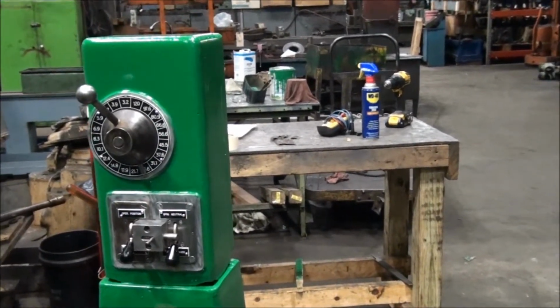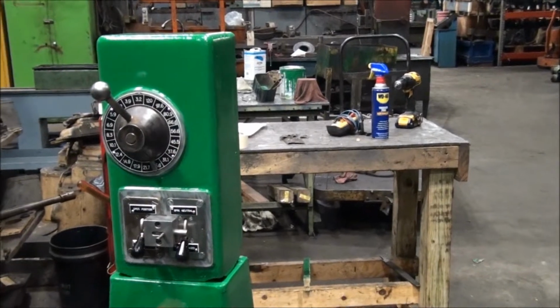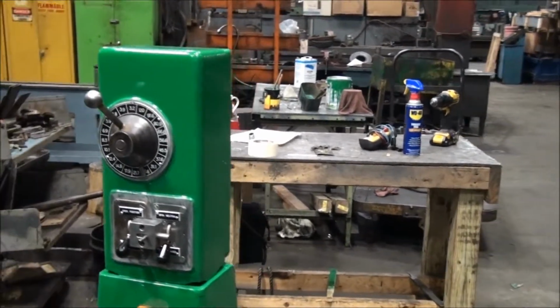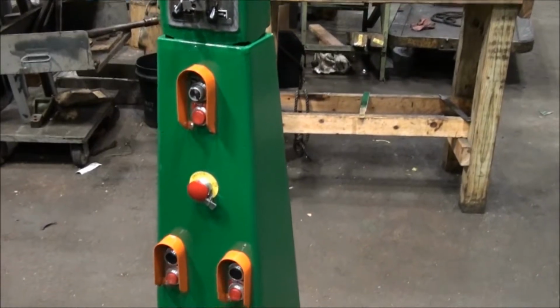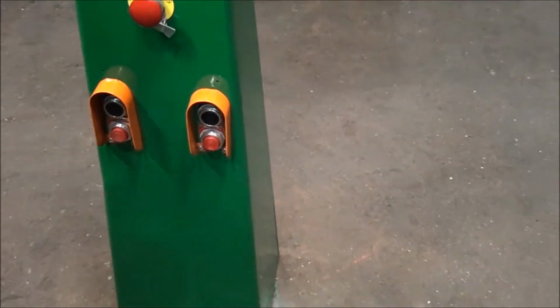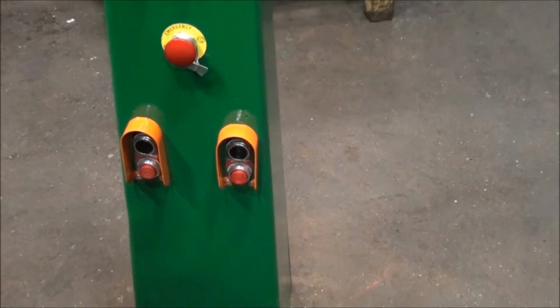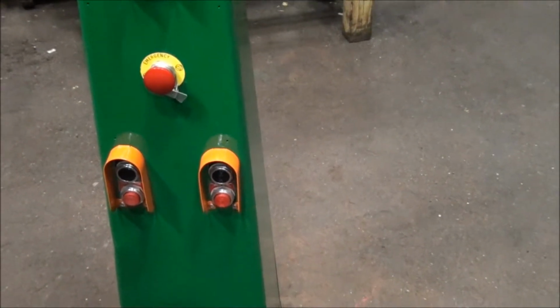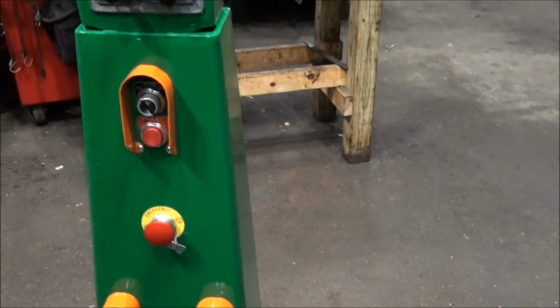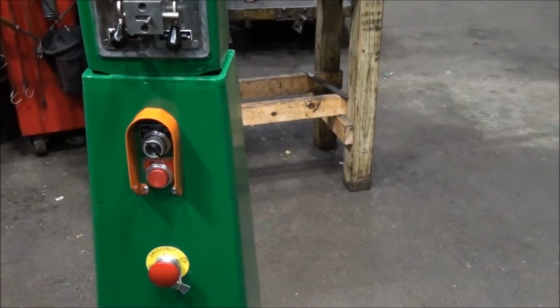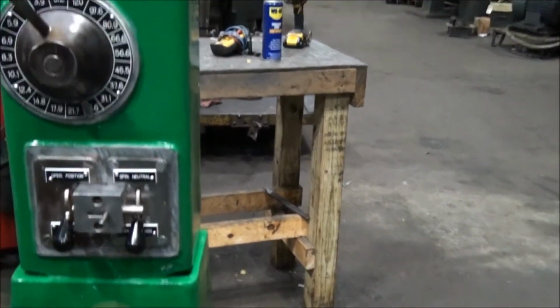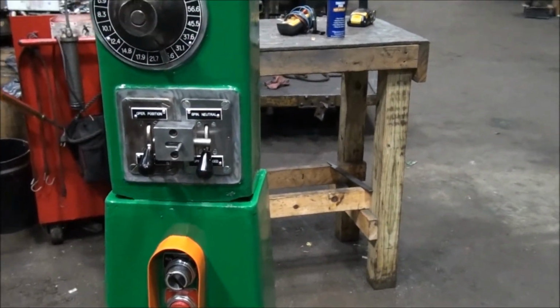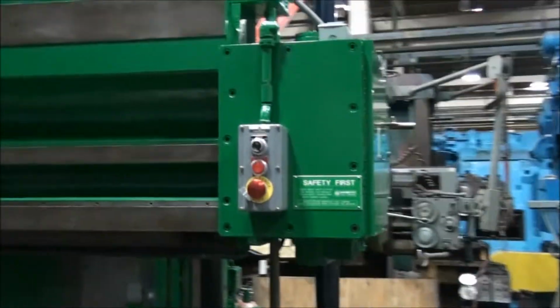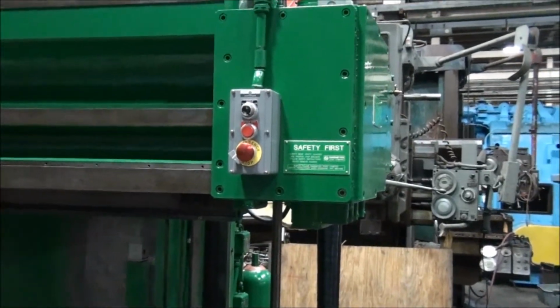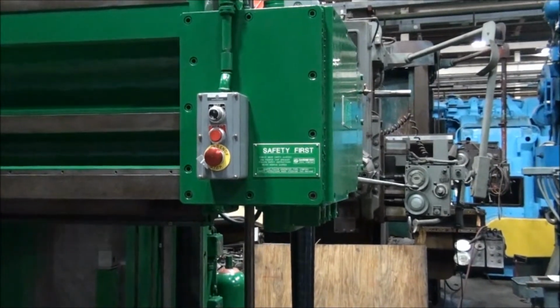assembly where we have an outside motor-driven hydraulic system installed. The machine is a 3.2 to 120 RPM machine with 20 speeds. We also have a main drive start-stop, a coolant start-stop, which is not supplied this application, but the electrical is in for it, an e-stop push button and spindle run jog commands, as well as a standard Bullard function pendant, which allows table neutralization. We also included an emergency stop push button on the cross rail feed box.